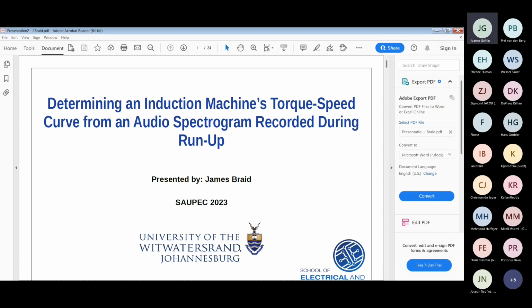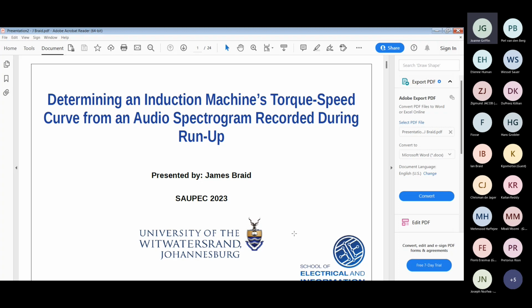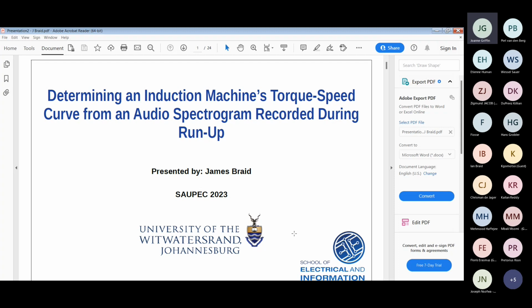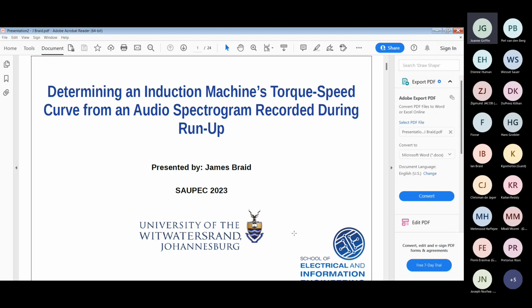So here we are. What we're going to do is determine an induction machine's torque speed curve, and you're all very familiar with why the torque speed curve is so important, particularly for induction machines. How we're going to do it is different - we're going to do it using an audio spectrogram, from the sound that the machine produces. I'll explain why we did it that way this time. And obviously the test is done during run-up.